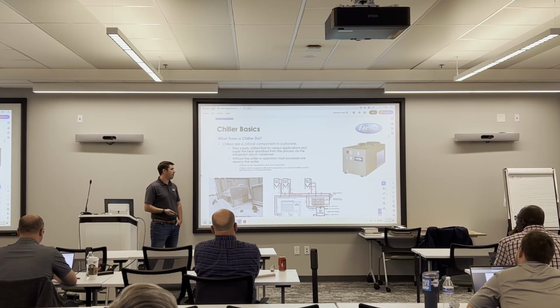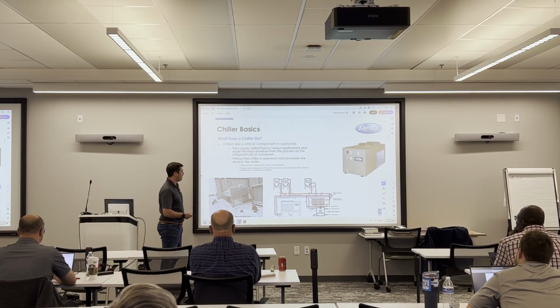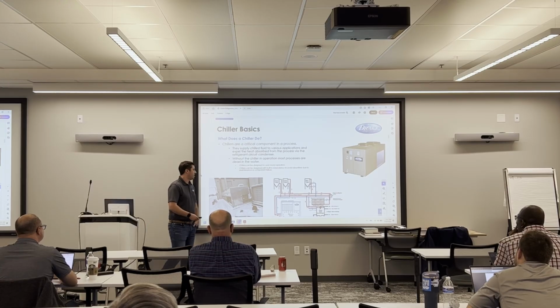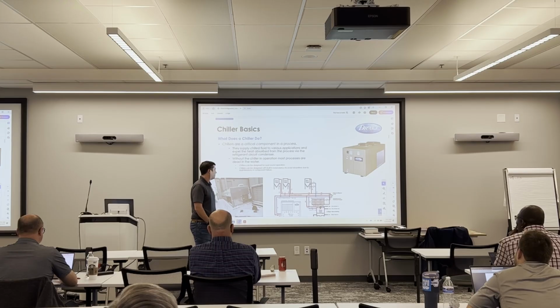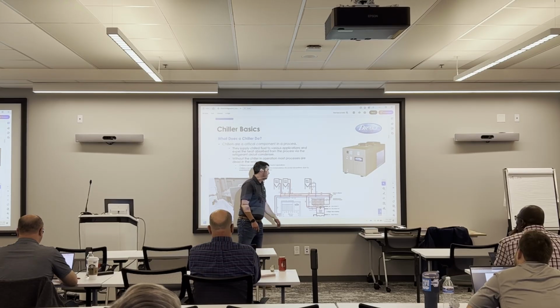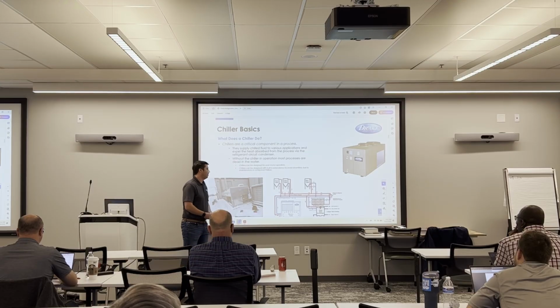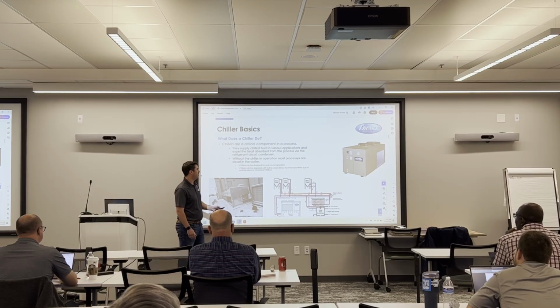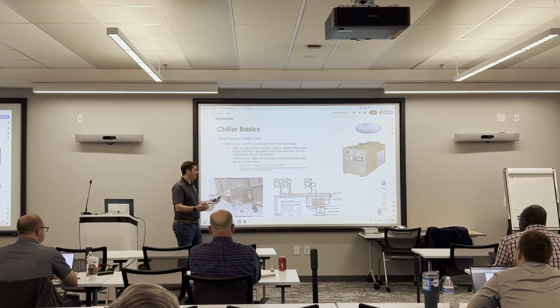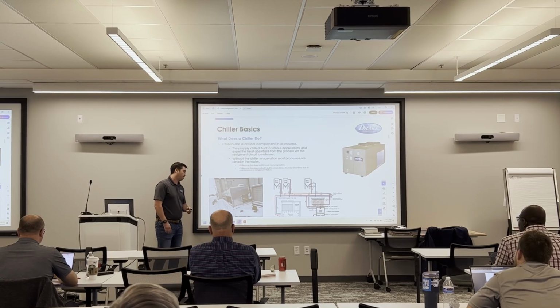If you don't have cooling, you can't run the machinery. I have a little graphic down below. This is what a chiller would look like in a brewery, either large scale or small scale. So all breweries are set up the same way. They've got fermentation vessels, they've got bright tanks, which are essentially storage tanks for the beer. You can probably drink right out of the bright tank if you wanted to. You've got different types of air handler coils in a brewery. So if you have a cold room, you want to store your kegs or your cans of beer, you can certainly do that. And then you also have a two-stage heat exchanger. We call that a two-pass heat exchanger.